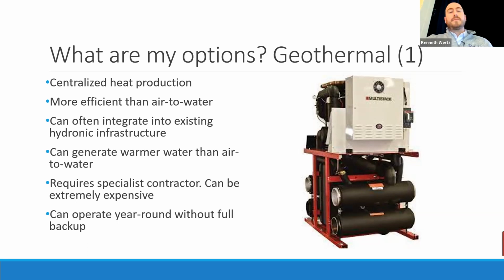And because we're talking geothermal, it's going to be very, very expensive. So you've got to potentially be drilling hundreds or more holes in the ground to put the pipe in for the geothermal field. And then that's an added cost on top of what you would have already been spending in the building for other options here. But the good thing is they can operate year round. You don't necessarily have to have that natural gas backup.